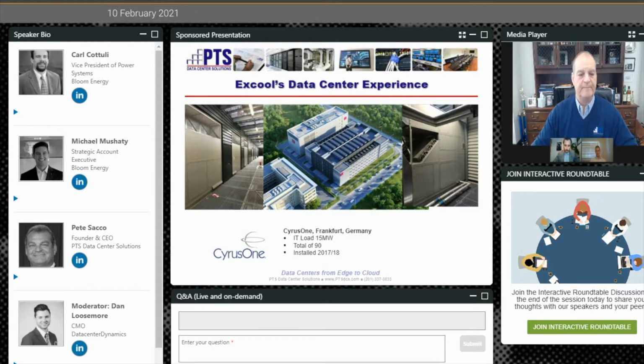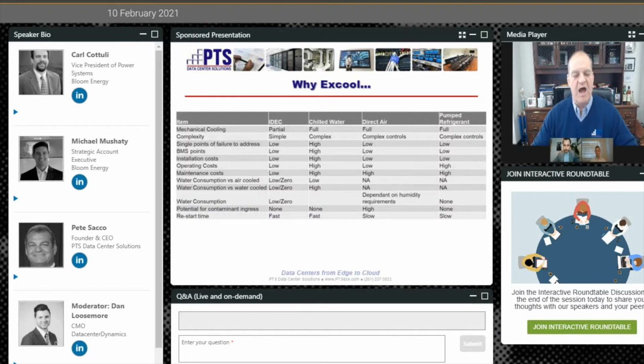So why, of all the choices—and there are some really good low PUE evaporative cooling solutions—did I latch on to this one? Because for me, the design checks all of the boxes. I can reduce my mechanical cooling to partial, depending on the operating condition, and it works directly with adiabatic indirect cooling, or without it, or with free cooling on the outside.